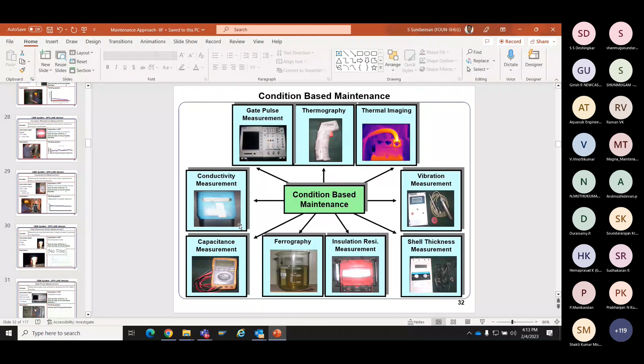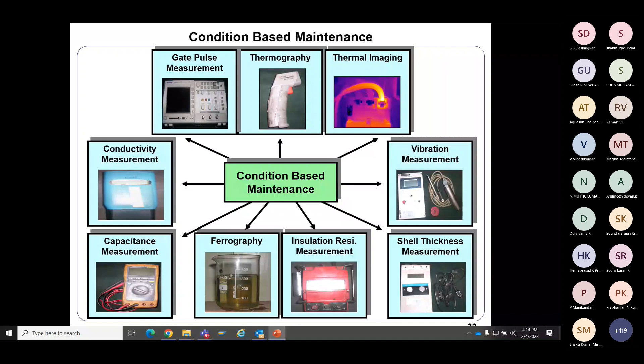You can see the screen here, this is thermal imaging where there are three phases in a contactor, R, Y, B. If you look at R and Y, this is not a physical measurement like degrees Celsius, but if you see the difference between R, Y and B, it is very bright, meaning the heat energy at the B phase is much higher compared to the rest. When you do this on a regular basis, you will know what is normal, and once you see a deviation...